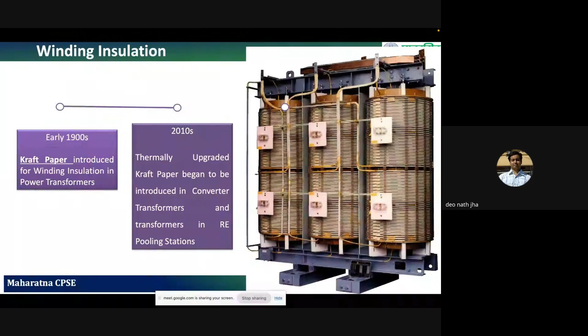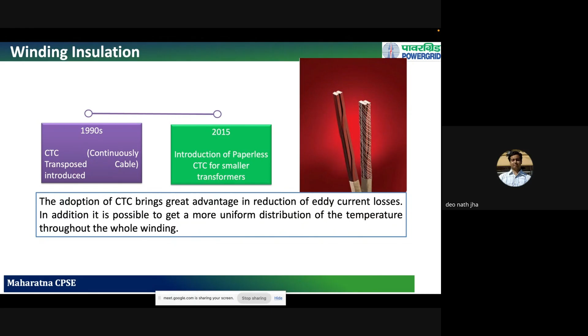Then in winding insulation, in the 1990s, continuously transposed cable was introduced. And now in 2015, for smaller transformers, we have gone for the introduction of paperless CTC. The adoption of CTC brings the advantage of reduction of eddy current losses. In addition, it is possible to get a more uniform distribution of temperature throughout the whole winding of the transformer.